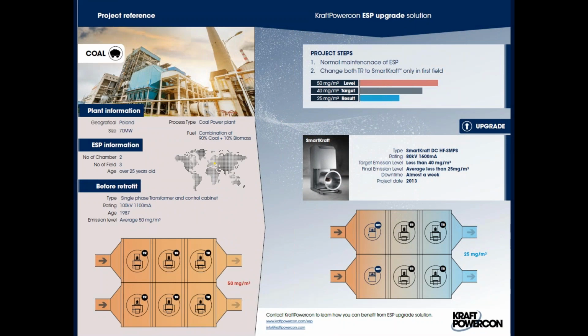Another case study: a coal-fired power plant, a smaller one, 70 megawatts. We did some normal maintenance of the precipitator, nothing major, but basically changed the inlet fields from a single-phase TR set to an SMPS. They were running 50 milligrams per normal cubic meter and needed to drive that under 40—we got it to 25, giving them a little margin. Another successful project showing you don't necessarily need to upgrade all your fields; you can just do a couple.